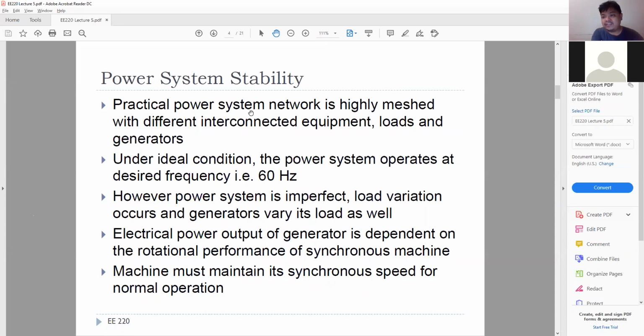Now, if we have a frequency that is grossly imbalanced, what happens is the generator has its own protection mechanisms and will try to isolate itself, or trip itself. It will trip itself rather than get damaged, because if the frequency drops too much, it will chase after that frequency so that it can operate and compensate for that drop in frequency.